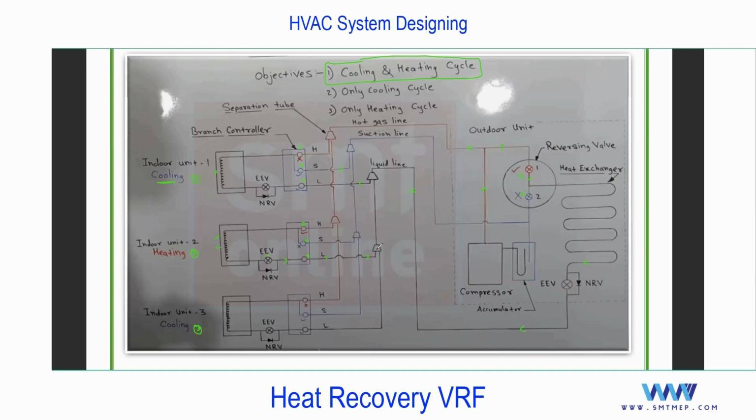So you see it can go back to the unit or else we can utilize it for this room 3 which calls for cooling. But this can be achieved, as I said, with the complete control system, with the opening and closing of the valve, with the complete microprocessor. But you see at this point the refrigerant is in the liquid state, means after condensation.